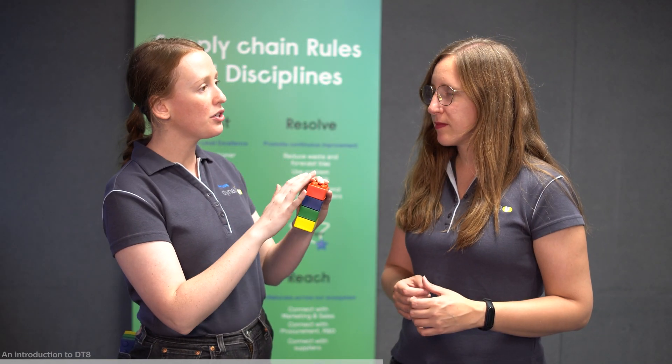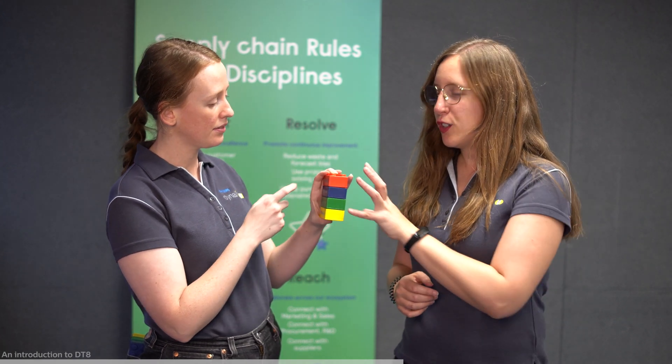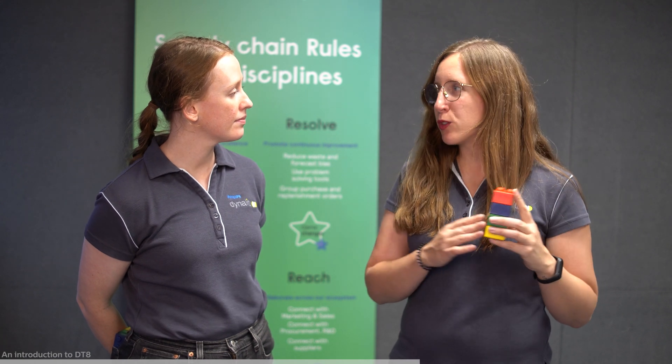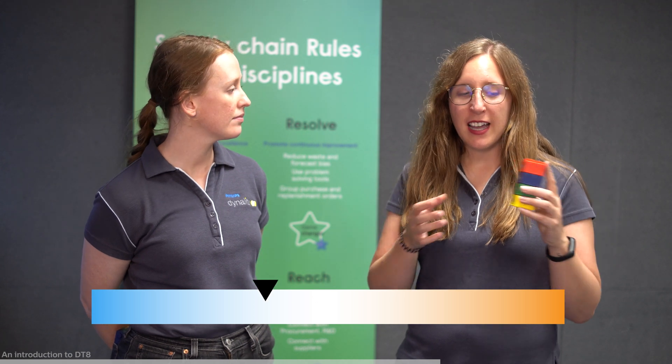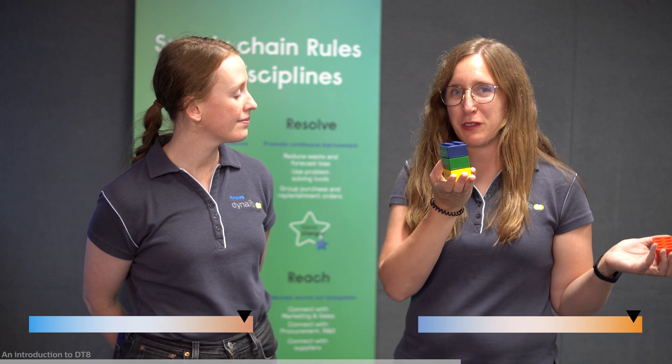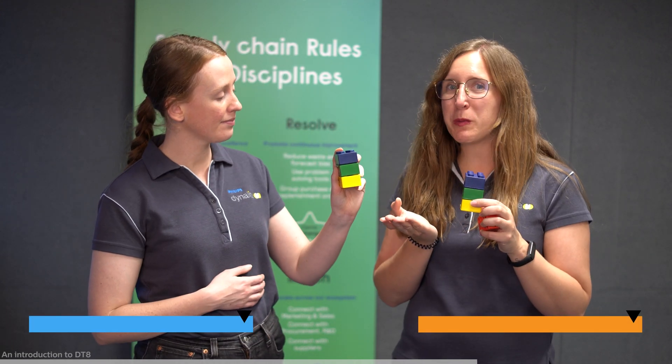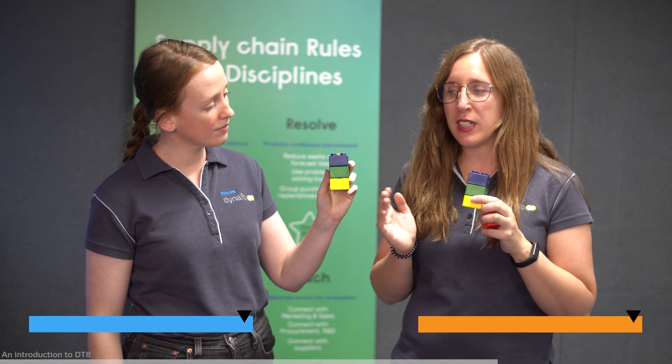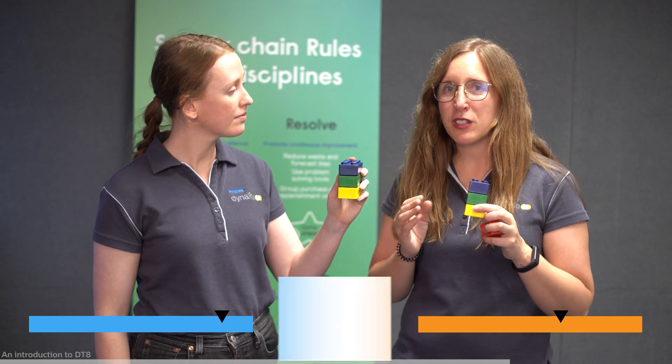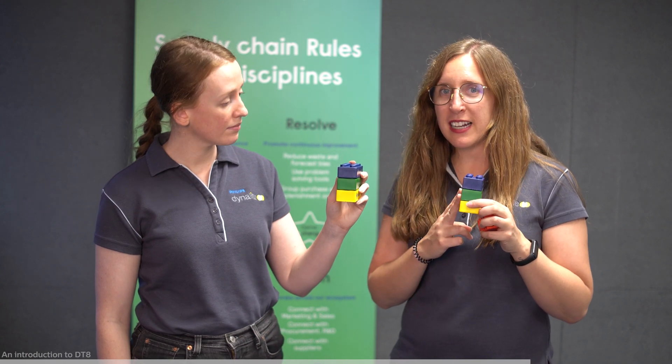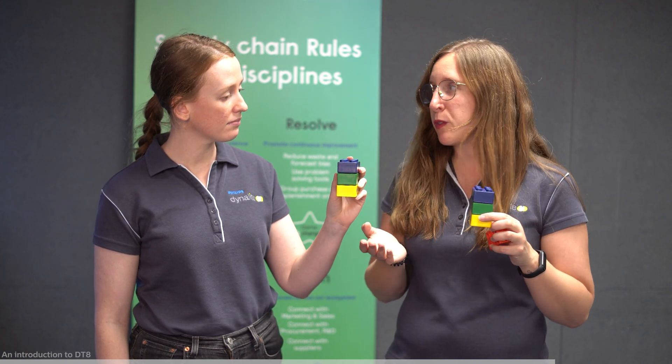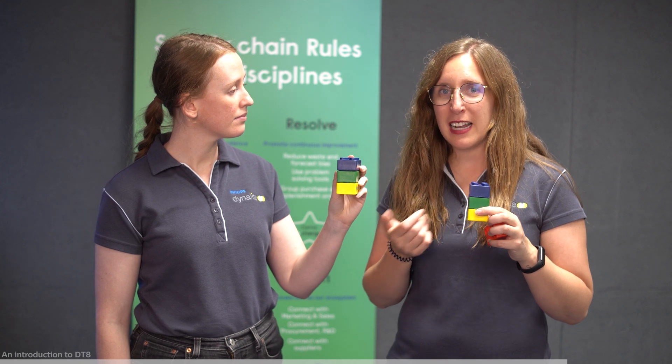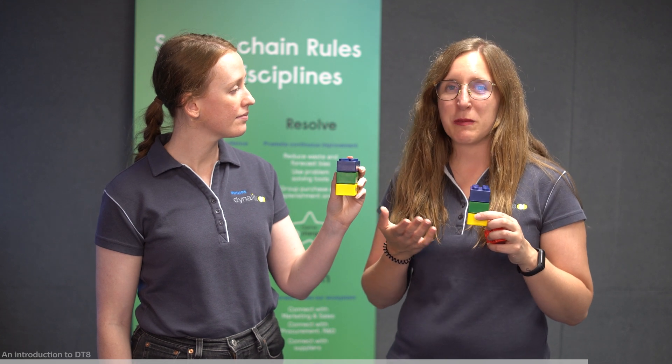So if we want to do color control in our project do we need a DT8 module? Not always this is one of the options but for example let's think about tunable white. Tunable white is really simple it's a scale between warm white and cool white and if we would like to remove this module the only problem is that I would need to duplicate the amount of blocks like this one. I've got another one right here. Perfect so yours would be cool white while mine would be warm white. If we want to achieve a color in between we would need to attune our light outputs to achieve the preferred color. This means that we would need double the hardware, double the DALI addresses and double the power consumption. Also presumably we will increase the amount of DALI controllers if we would have a lot of luminaires like these ones and the labor cost because we will not only need to manufacture double the luminaires but also install them on site.